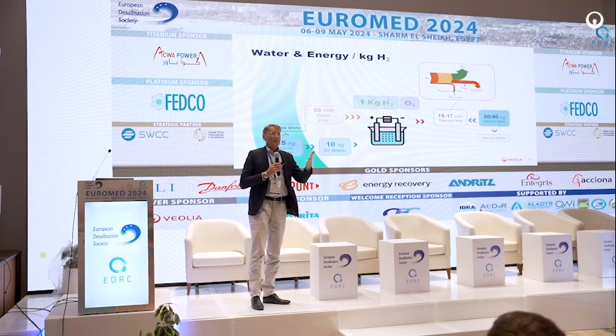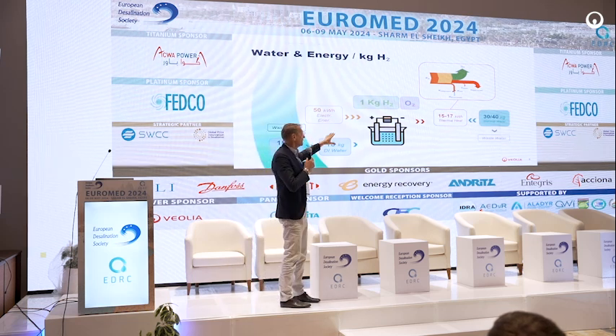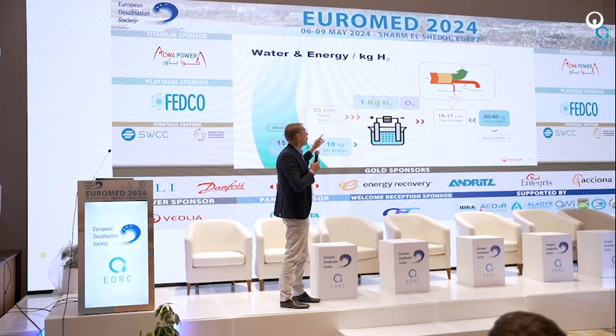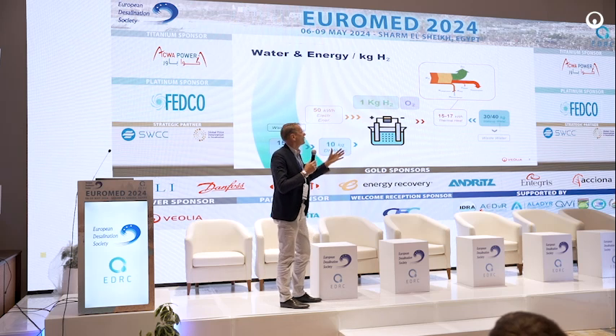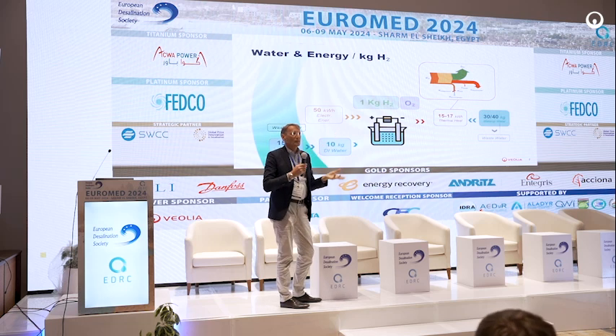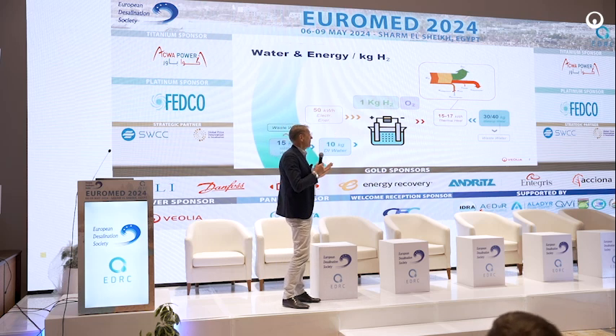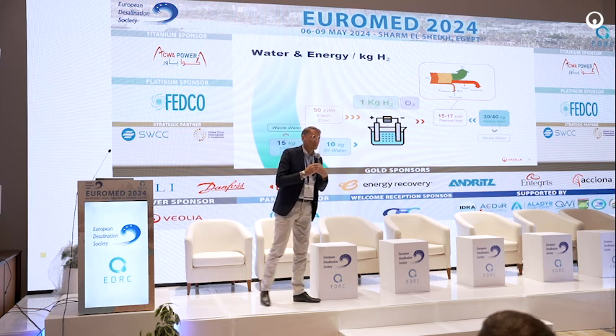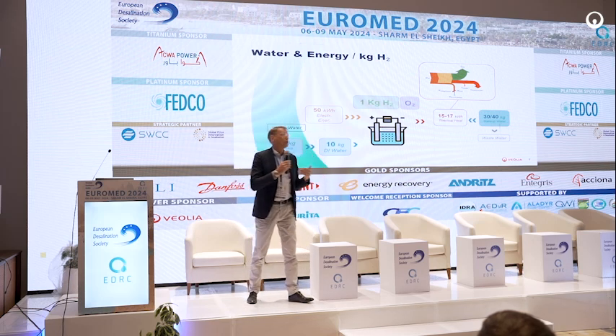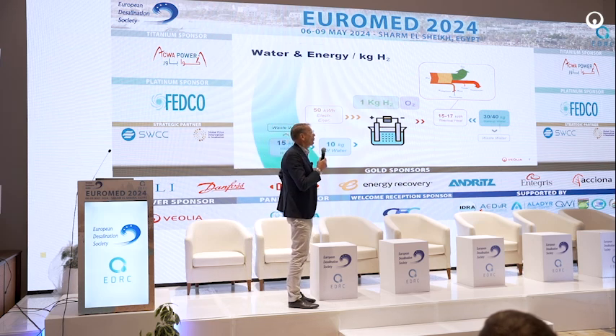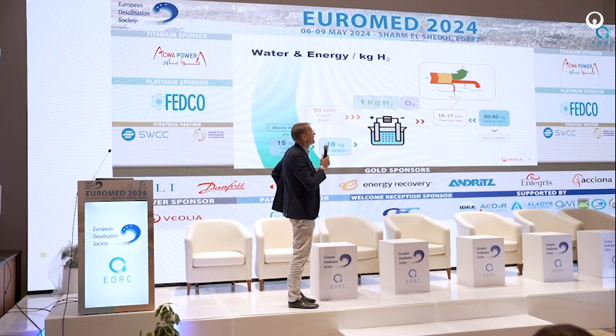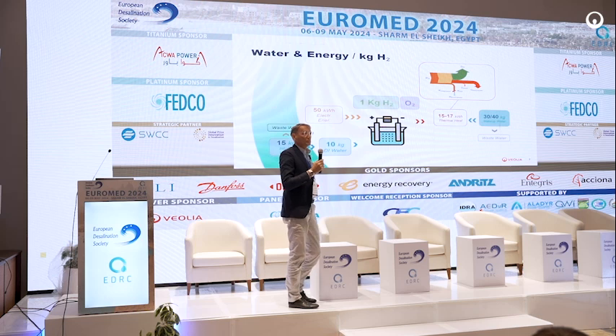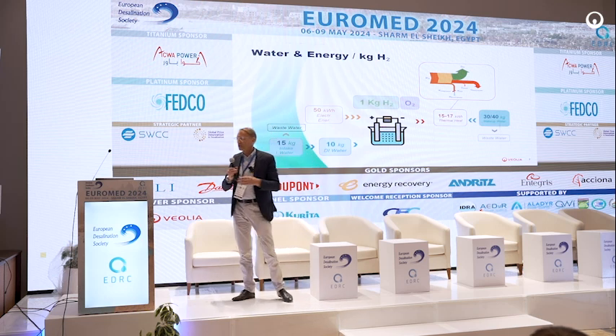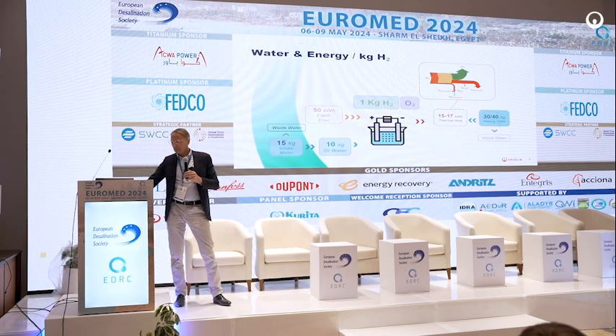We have extra heat, as was perfectly presented before—we have more than 1/3 of this energy that we are supposed to exchange. We call it waste heat. But if we need, for big plants, to use cooling towers, we need an extra 30-40 kilograms of makeup water. It depends on the cycle of concentration, it depends on the source.